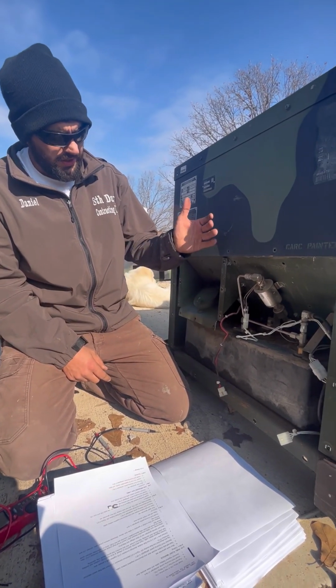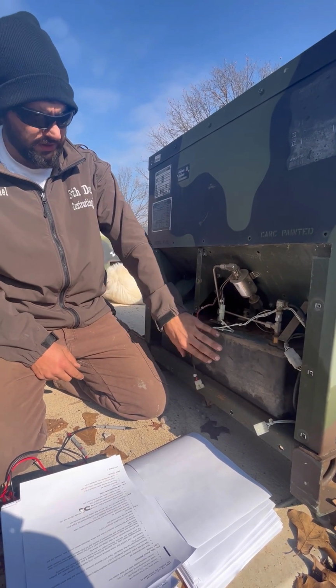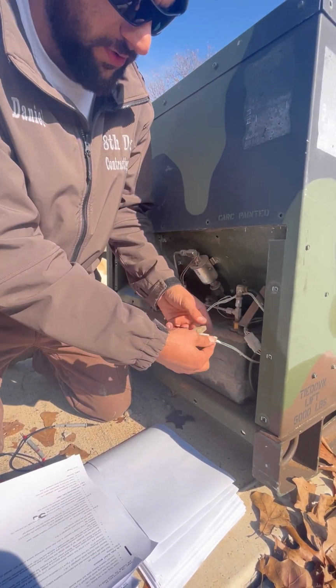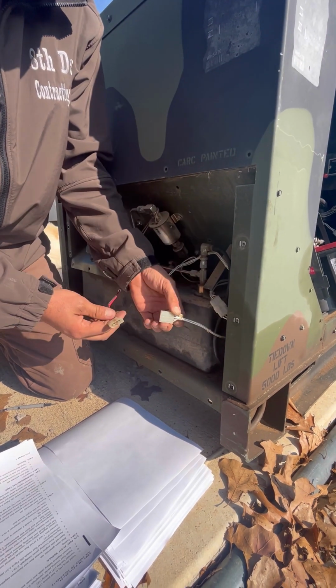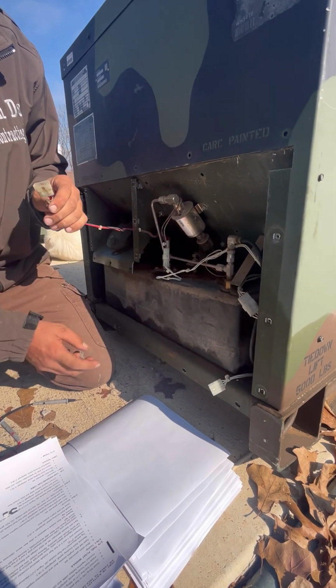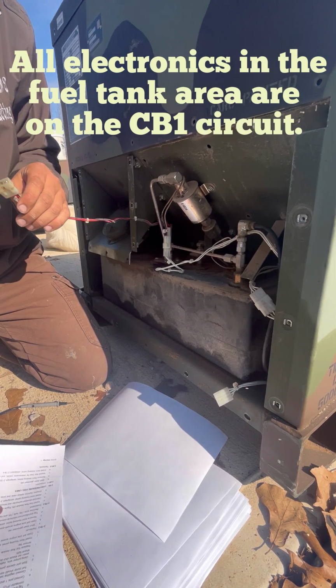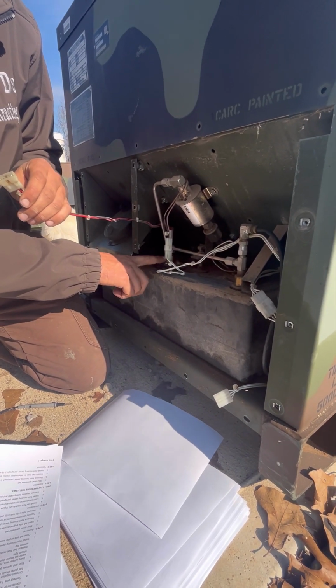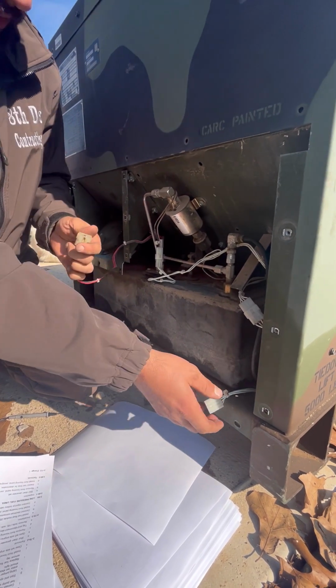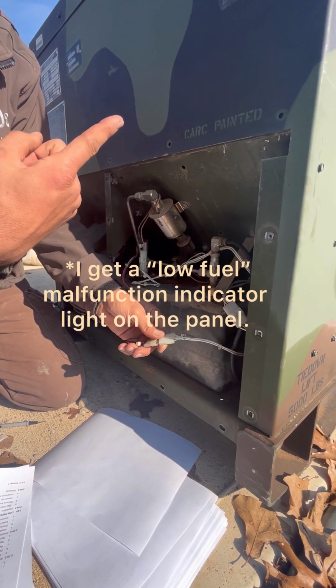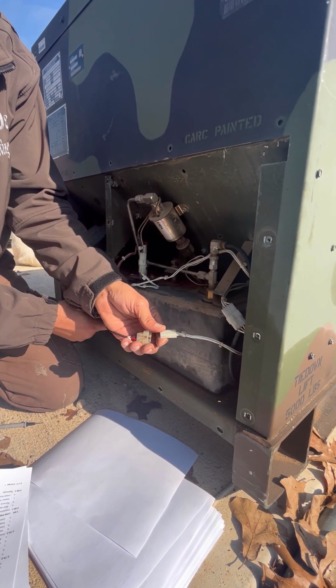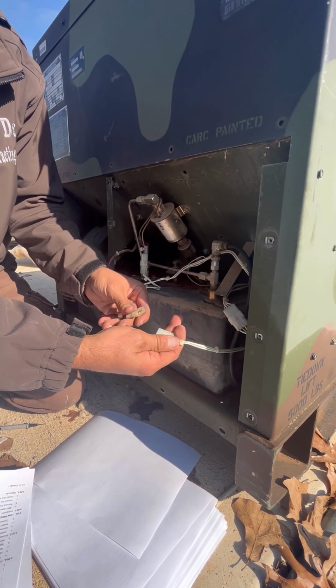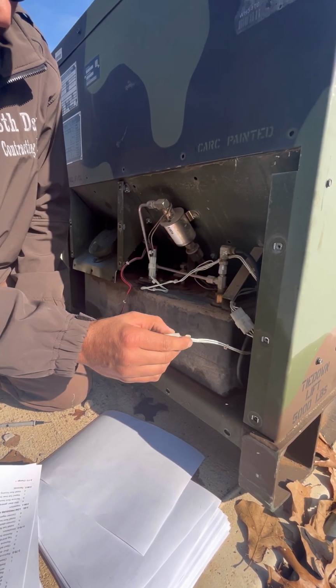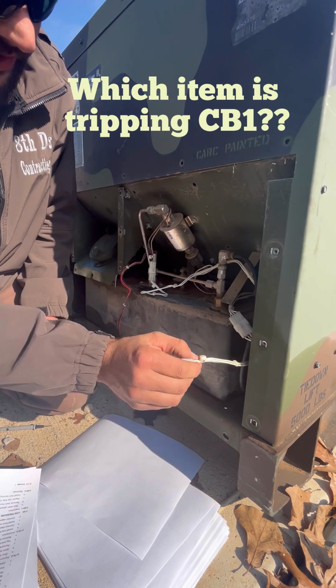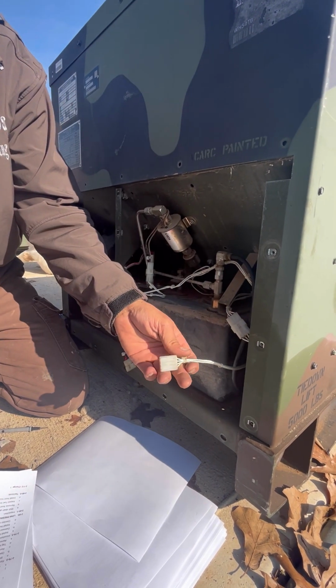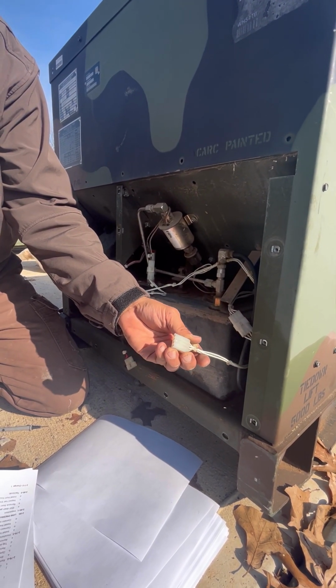I opened up the panel that exposes the fuel tank, and this is how I found it. These two were disconnected, and according to the manual, this is your fuel pump float switch right here. When you plug these in, you get an error code on the malfunction panel that says there's low fuel in the tank. If you disconnect it, I can start the generator, but I'm going to test and verify that. First, I'm going to start with the fuel pump float module, or the fuel float module here.